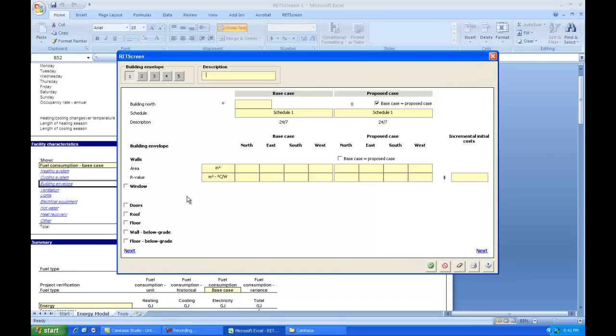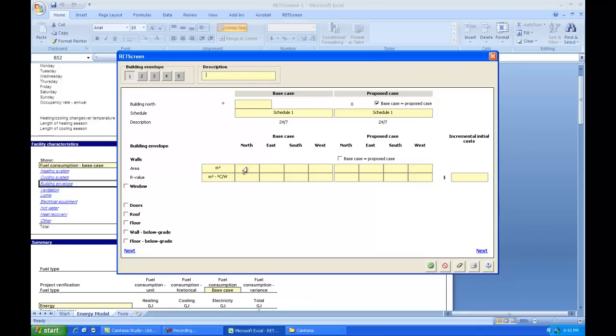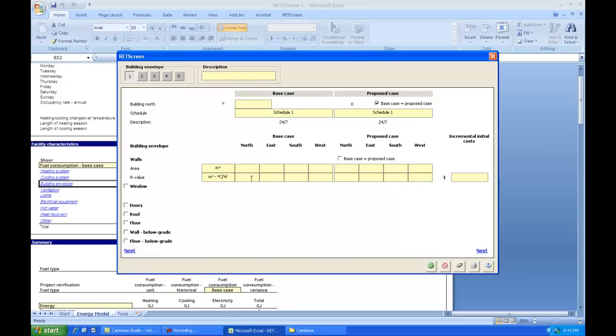There are certain things I can't do on one button though. I have only above grade walls. I have one section here to do above grade walls. If all of them are going to have the same R value, at least all the ones facing north will have the same R value. If I have more than one kind of above grade wall facing north that might have two different R values, I would be smart to put those on different buttons. One on button 1 and one section on button 2. That relieves me from the difficulty of having to come up with an average R value for two different pieces of wall.